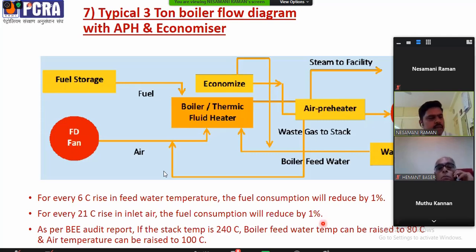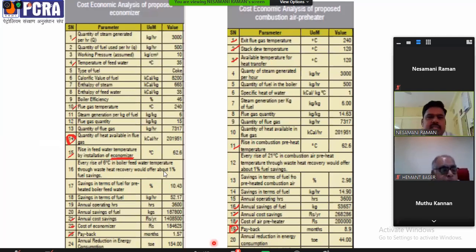So as per a BEE report, if the stack temperature is 240 degrees Celsius, the boiler feed water temperature can be raised to 80 degrees Celsius, and the air temperature can be raised to 100 degrees Celsius. So this is the BEE energy audit report. This is not clear, so I will explain it. They have done this on a 3-ton boiler. The temperature of the feed water is 35 degrees Celsius, but the flue gas temperature, meaning stack temperature, is almost 240 degrees Celsius. We have a buffer.